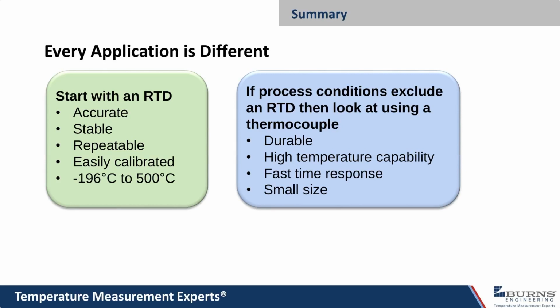Every application is just a little bit different. But I always like to start out with an RTD to see if it will fit in that application. We've made the decision to measure the temperature, so we may as well do it the most accurate, best way possible, and that's typically with the platinum resistance thermometer. They're very accurate, stable, and the measurements are fairly repeatable, and you can also pull it out of the system and calibrate it very easily. Temperature range, -196 with liquid nitrogen up to 500 C, is pretty much a standard industrial type range. There are RTDs that will go over 500 C. Those are typically used in laboratory applications, though.